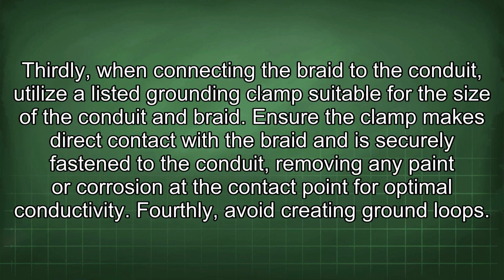Thirdly, when connecting the braid to the conduit, utilize a listed grounding clamp suitable for the size of the conduit and braid. Ensure the clamp makes direct contact with the braid and is securely fastened to the conduit, removing any paint or corrosion at the contact point for optimal conductivity.